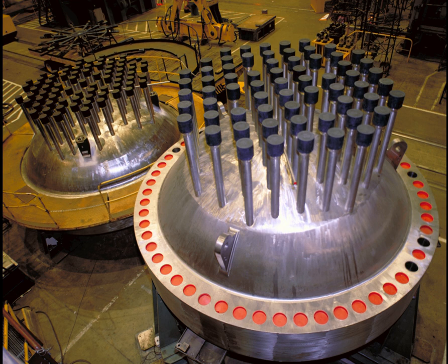The coolant is pumped around the primary circuit by powerful pumps. After picking up heat as it passes through the reactor core, the primary coolant transfers heat in a steam generator to water in a lower pressure secondary circuit, evaporating the secondary coolant to saturated steam — in most designs 6.2 MPa (60 atmospheres, 900 PSIA, 275°C / 530°F) — for use in the steam turbine. The cooled primary coolant is then returned to the reactor vessel to be heated again.